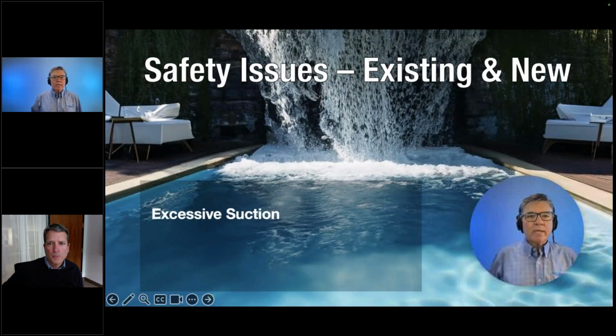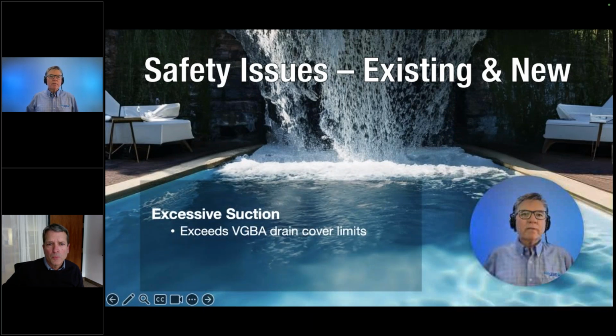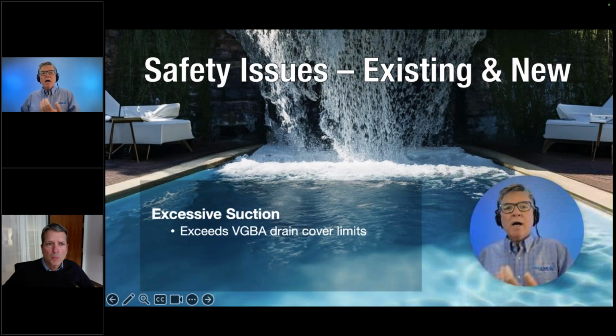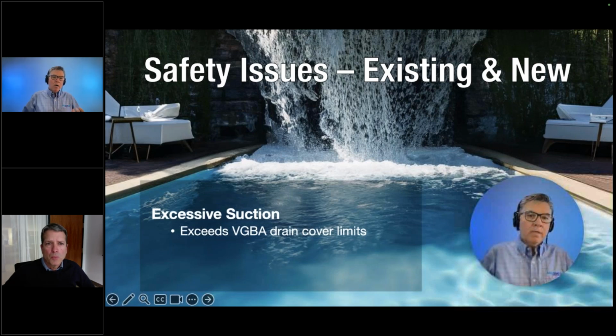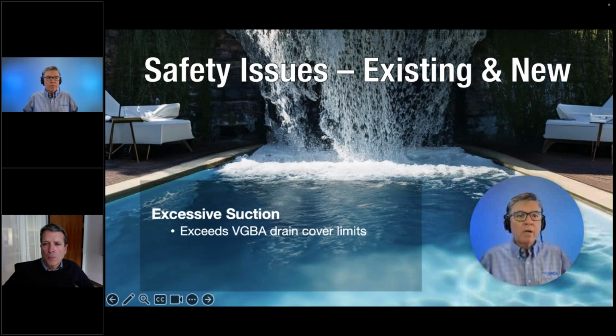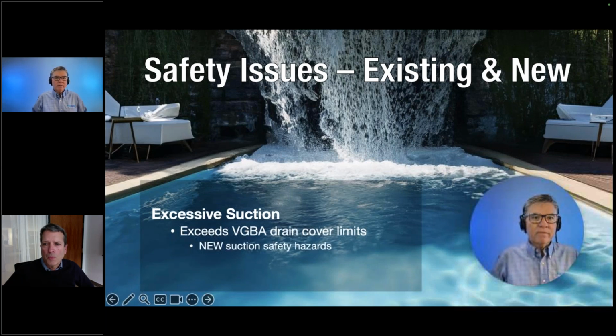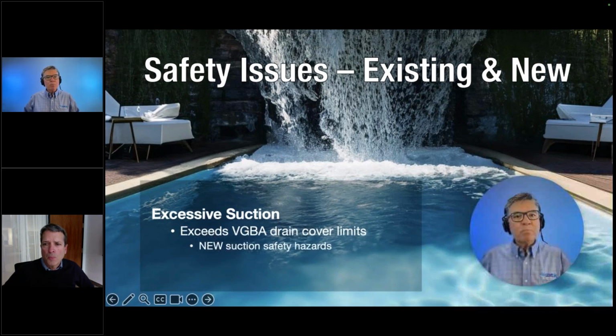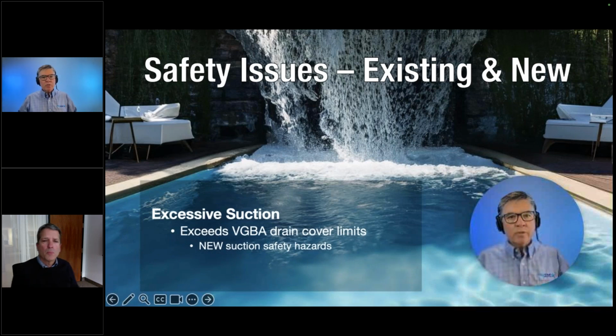So that's cavitation. Now let's look at another safety issue, and this can be an existing problem that you are inheriting by replacing the pump, or you're creating a new one because now you have a higher performing pump on a suction system and piping system that can't handle it. So now you get to a much higher flow rate than the original designer contemplated. So we're exceeding the VGBA limits. That would be a new suction hazard.